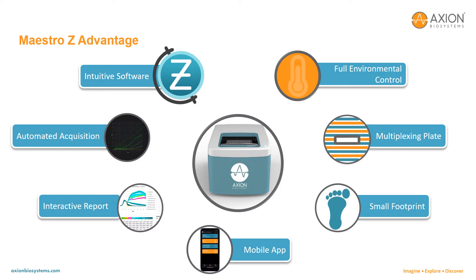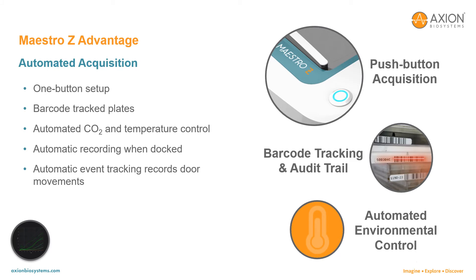Axion's Maestro Z is a bench-top size instrument with a built-in incubator for fine control and tracking of temperature and CO2. The viewing window in the plate allows for multiplexing with other assays. The small footprint means it doesn't take up much space in the lab. The software is intuitive with automatic data acquisition, interactive reports, and you can even use a mobile app to monitor your experiments remotely. You start the assay with the push of a button to dock the plate into the Maestro Z, which automatically triggers regulation of temperature and CO2 levels. The plate usage is logged via an integrated barcode scanner for convenient experiment tracking.